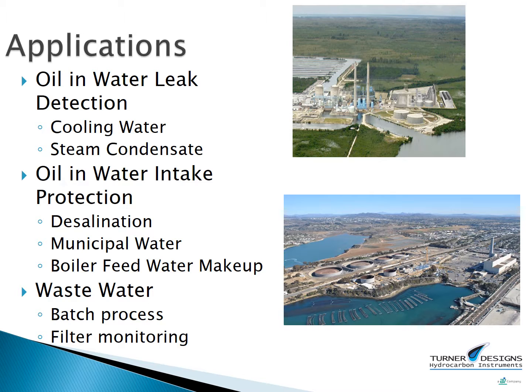The TD120 is also good for protection of intake waters to desalination plants to protect the reverse osmosis membranes or other systems from fouling, municipal water, and boiler feed water makeup where the source is a river or a lake or ocean. The TD120 can be used in wastewater processes where there's a batch process or a polishing filter.